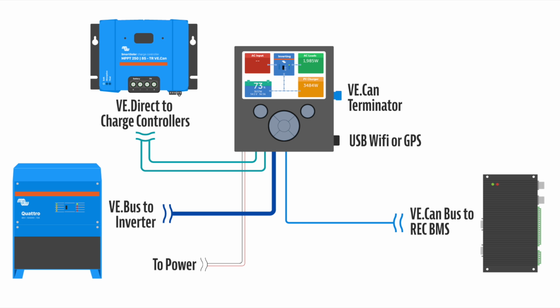To connect your inverter, use a VE bus or Ethernet cable, and for the MPPT solar charge controllers, use VE direct cables. The display also needs power, so connect its positive and negative wires to the positive and negative of the system. You may need to put a terminator plug into the second VE CAN slot—it does come with one. And if you want to run the VRM portal full time, a USB Wi-Fi adapter will allow you to connect the display to your network.